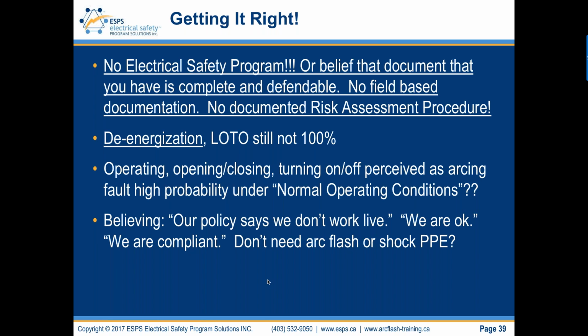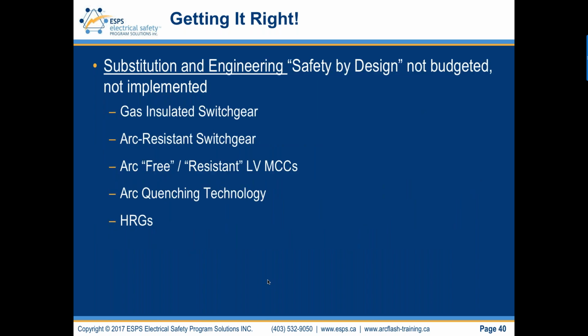So we've got to ensure that you don't believe a policy and a statement means your company doesn't need 70E or Z462. Energized electrical work is required. We need it. We can't use energized electrical equipment without it. Substitution, engineering. So I mentioned earlier that there's gas insulated switchgear, arc resistant switchgear now. There's arc resistant low voltage MCC designs, arc quenching technology, and high resistance grounding, which has been around for a long time. It has a whole new home, right? High resistance grounding and its benefit to arcing fault probability and resulting arc flash.